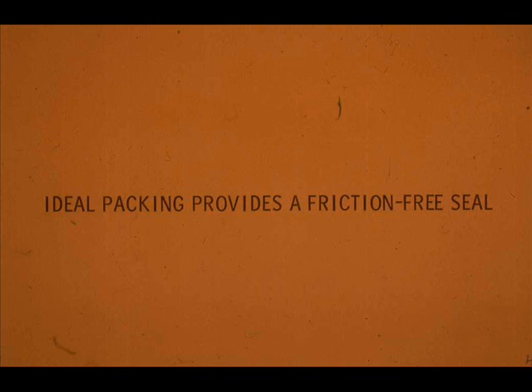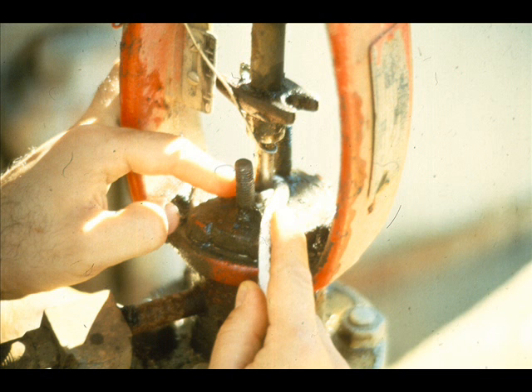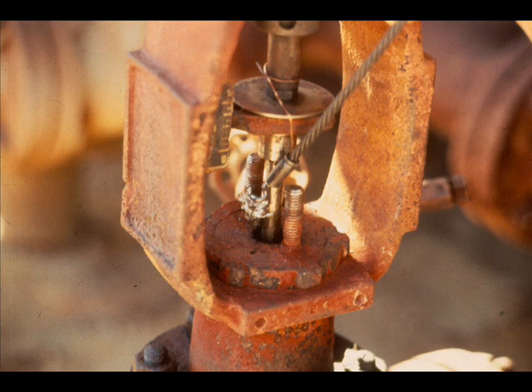Remember, packing should be as friction-free as possible. If you have to tighten packing excessively, it will create friction and wear out sooner. So, what do you do if you have to excessively tighten the packing to stop the leak, or the gland stud nuts tighten all the way down but the valve still leaks? You will have to add or, better yet, replace the worn or defective packing.